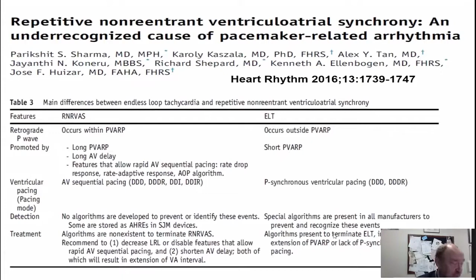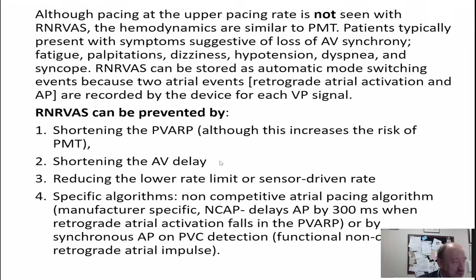These are the programming maneuvers that one can do to prevent RN-RVAS. You can shorten the PVARP, although on the other hand this increases the risk of PMT. You can shorten the AV delay, and you can reduce the lower rate limit.